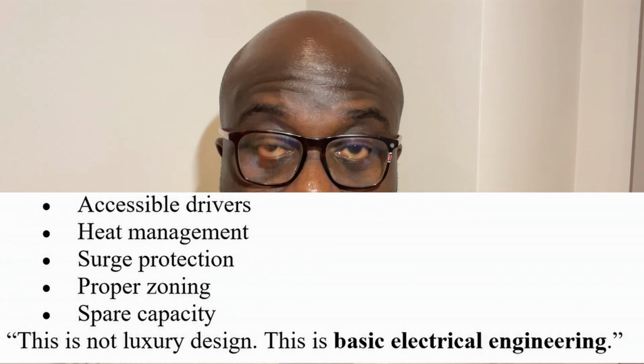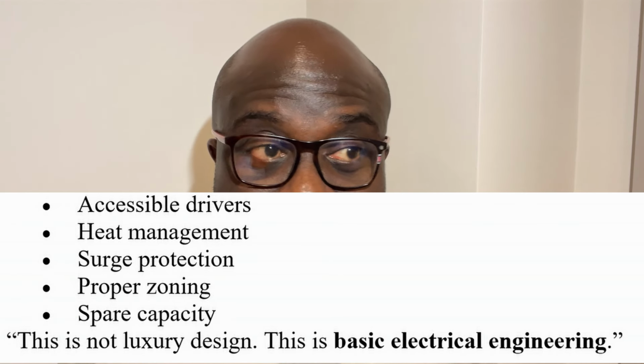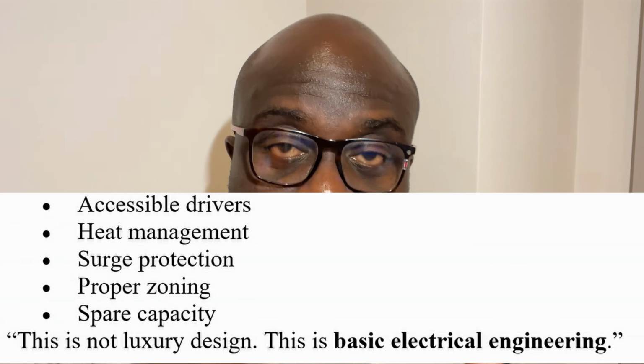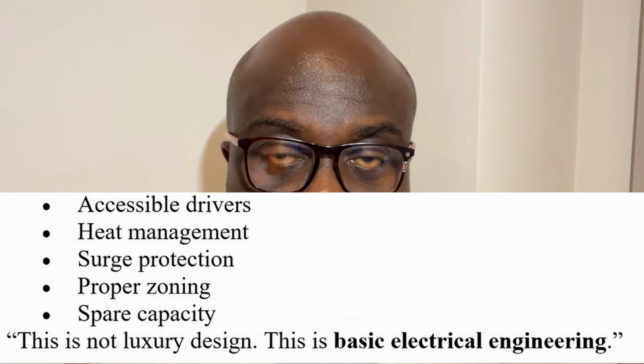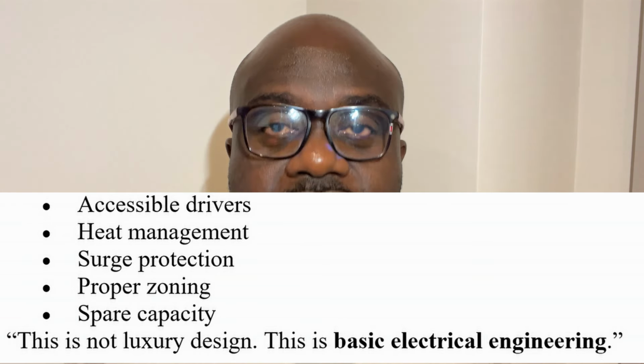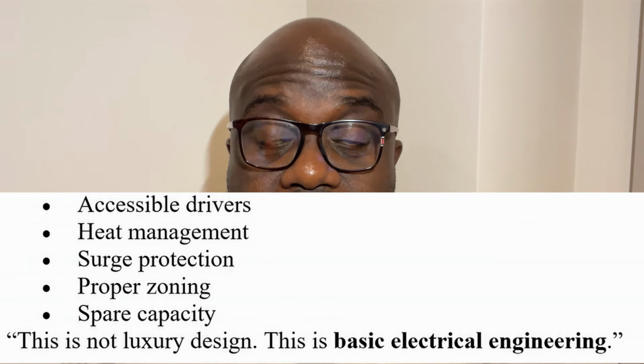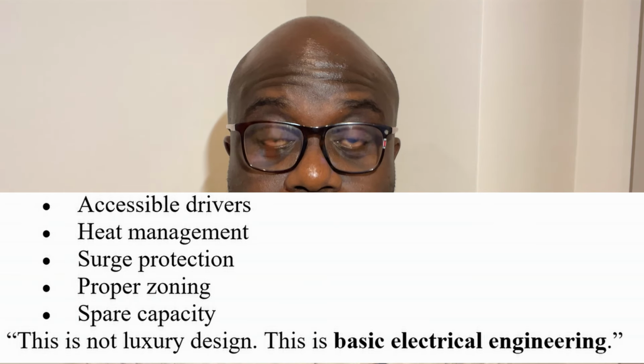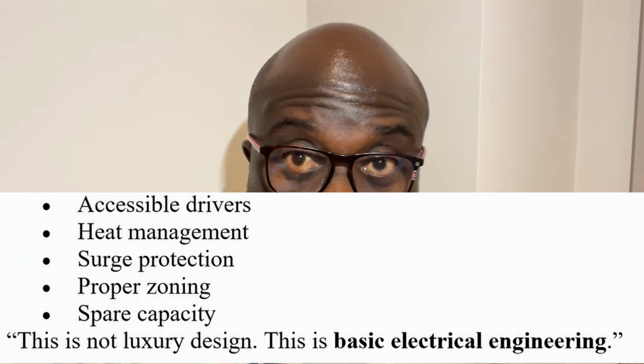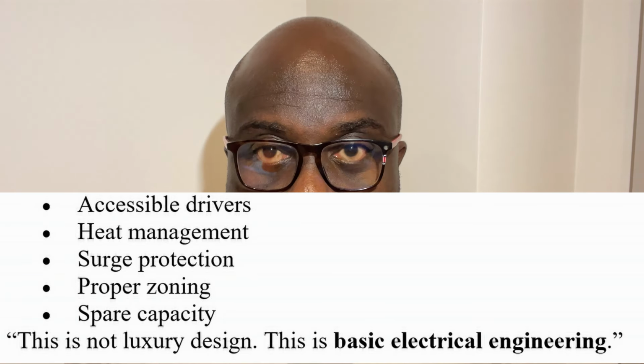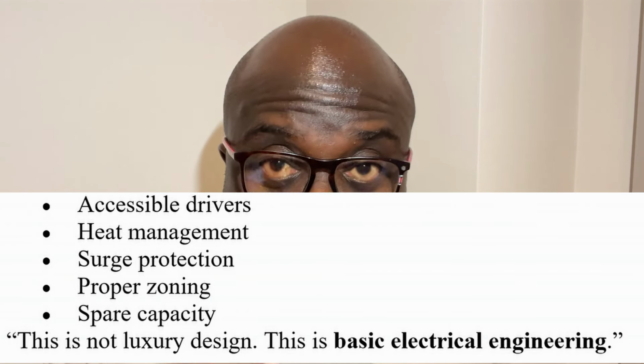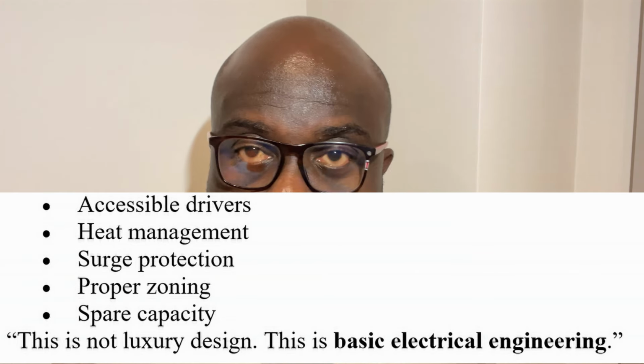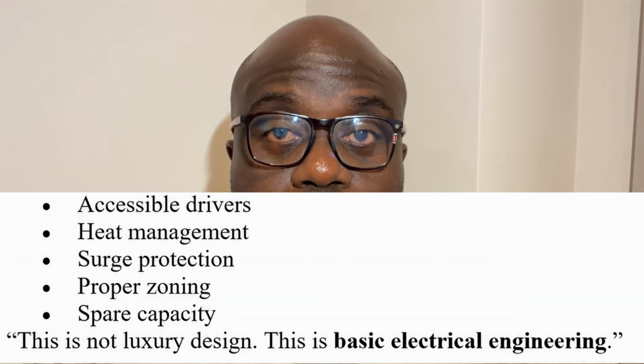Proper zoning: don't put an entire floor on one lighting circuit. Ensure you have spare capacity, spare breakers in a distribution board. If you go there after the building is finished and all of the breakers are connected, then there's an issue. There should be spare breakers, spare ways. Very, very important. The distribution board should not be fully occupied.